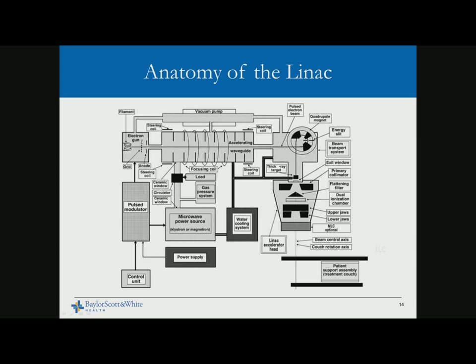The anatomy of the LINAC is important — I recommend all residents know this slide. We need to understand the major components of the LINAC before doing acceptance testing. The TrueBeam architecture is completely different from older machines. If you don't understand the anatomy, it is difficult to ask questions: how many targets, how many flattening filters, how many scattering foils, how many energy selections, and what affects what?